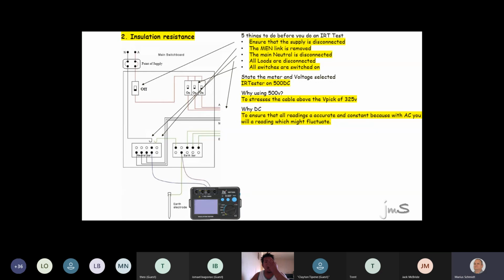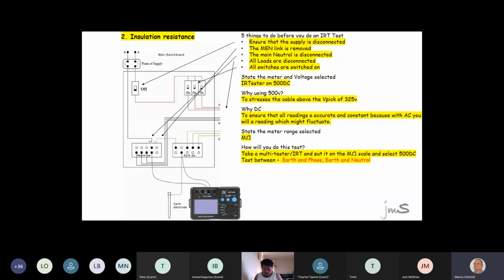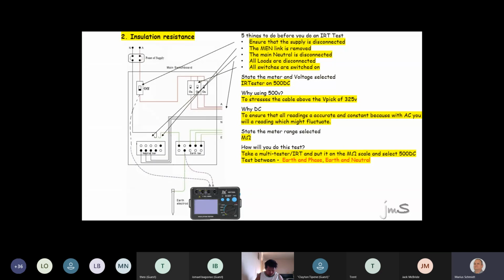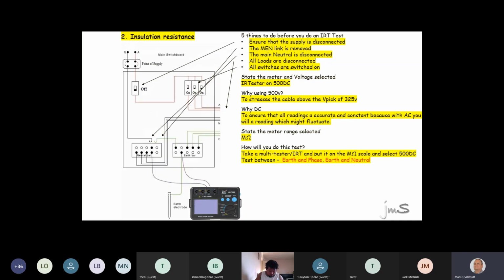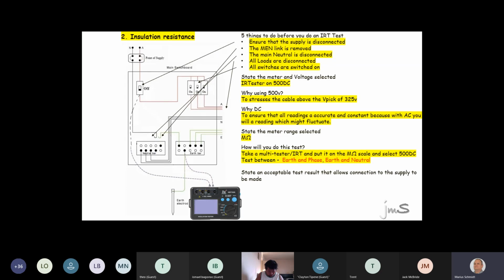Right, guys, I give you all the possible things they can ask. They might not even ask all that. They might only ask you what instrument will you choose. They might tell you only megohm scale. They might ask what's the maximum test. How will you do the test? You do it one on earth, one on phase. One on earth, one on neutral. And you press test. Once you press test, all your readings, see there's one between phase and neutral, and there's one between earth and phase. Just earth and neutral, earth and phase. See that? Earth and neutral, earth and phase. And all readings shall be greater than how many megohms? 1 megohm. But what happens if there was an element in the system, like a stove or hot water cylinder?